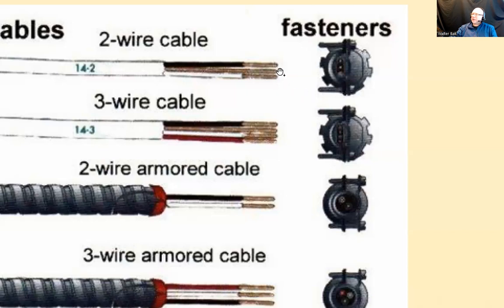So that's why we need to use the bonding wire. What we do is we connect that bonding wire to the grounding terminal in that metal electrical box. So that metal electrical box is grounded. It's not just hanging in the air. So when by accident the hot wire detaches from the screw terminal and touches the box, the electricity is going to be drained to the ground through the safety or the bonding or the grounding wire, and probably is going to flip the circuit breaker. It's going to open the circuit breaker. Of course, there are no guarantees to anything, but this is how it's supposed to work. Current carrying conductors, there's a safety or grounding wire, bonding wire.